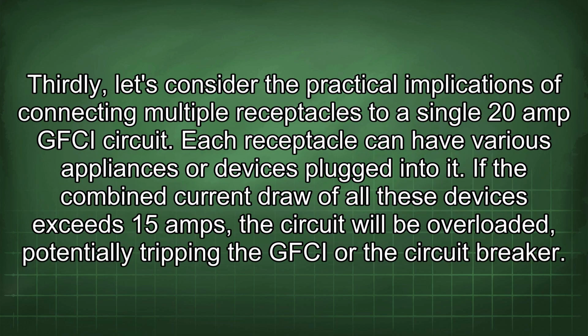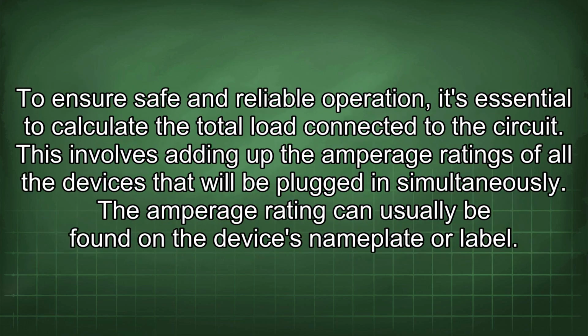Thirdly, let's consider the practical implications of connecting multiple receptacles to a single 20-amp GFCI circuit. Each receptacle can have various appliances or devices plugged into it. If the combined current draw of all these devices exceeds 15 amps, the circuit will be overloaded, potentially tripping the GFCI or the circuit breaker. To ensure safe and reliable operation, it's essential to calculate the total load connected to the circuit. This involves adding up the amperage ratings of all the devices that will be plugged in simultaneously. The amperage rating can usually be found on the device's nameplate or label.